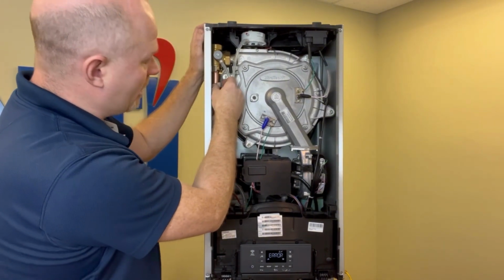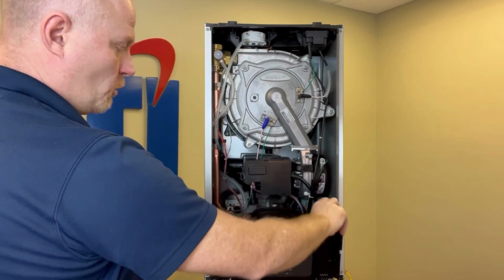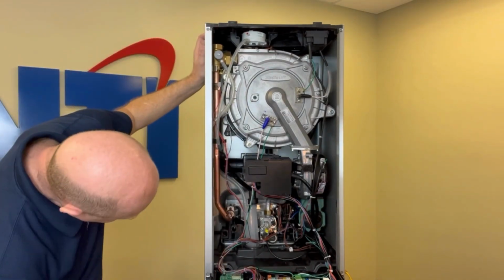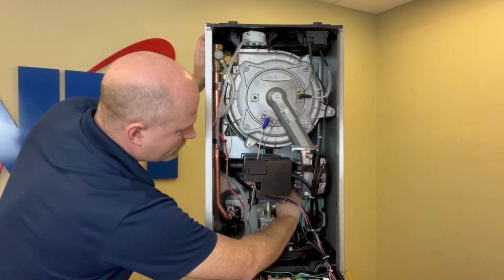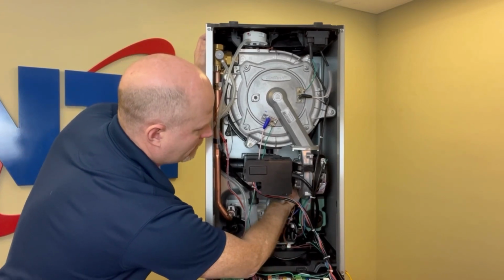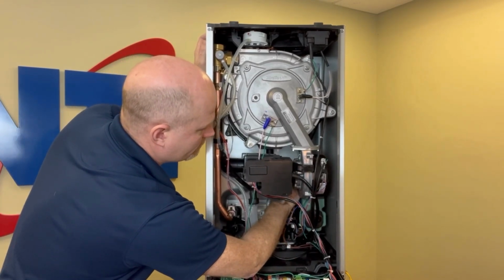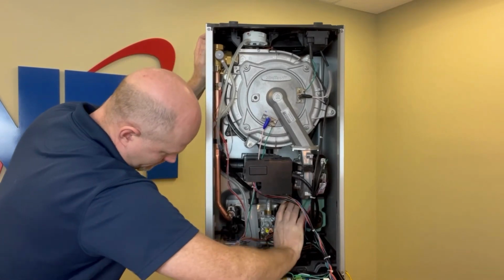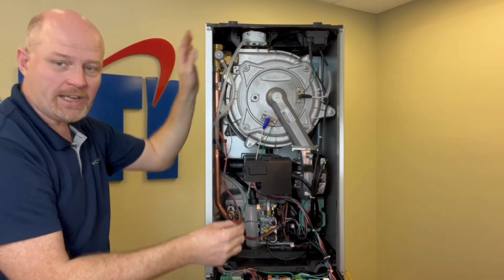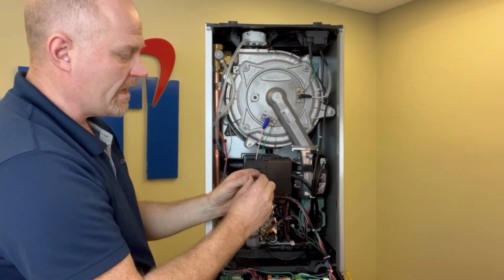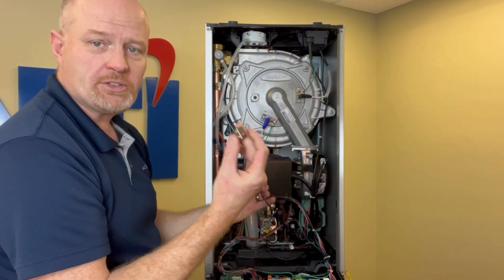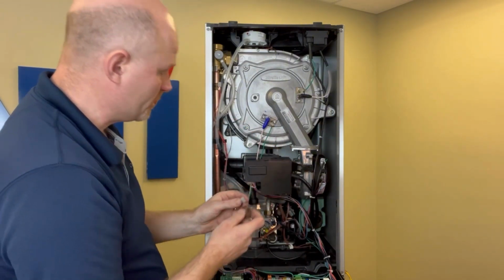Install the sensor on the pipe. That is your supply sensor. We'll open up the cabinet, and in the upper right-hand corner is the return sensor. So I'm going to remove that from the pipe and bring it out here where I can see it. Again, inspect the sensor carefully, make sure there's no defects in it or damage.